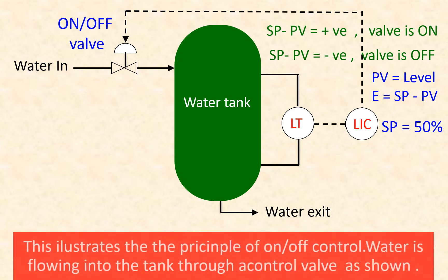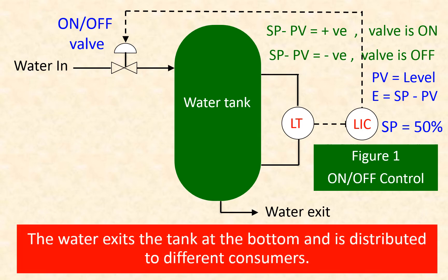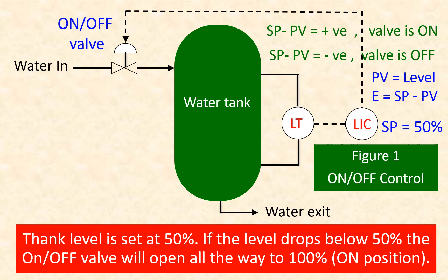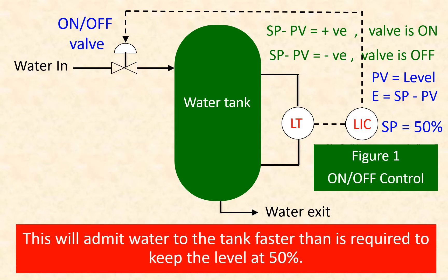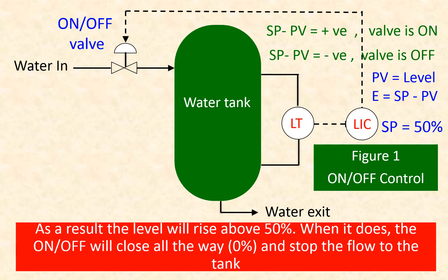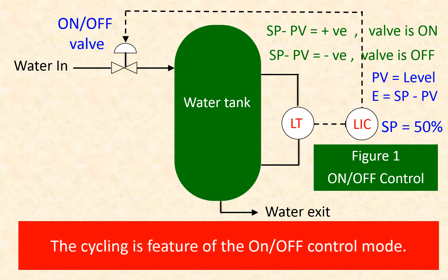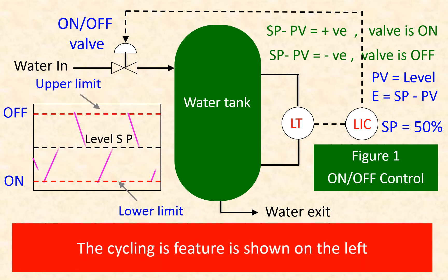This figure illustrates the principle of on-off control. Water is flowing into the tank through a control valve. The water exits the tank at the bottom and is distributed to different consumers. The tank level is set at 50%. If the level drops below 50%, the on-off valve will open all the way to 100%. This admits water to the tank faster than required to keep the level at 50%, so the level will rise above 50%. When it does, the on-off valve will close all the way to 0% and stop the flow. With no water flow, the tank level will drop and the cycle will repeat. This cycling is a feature of the on-off mode, shown on the left of the tank with the animation.